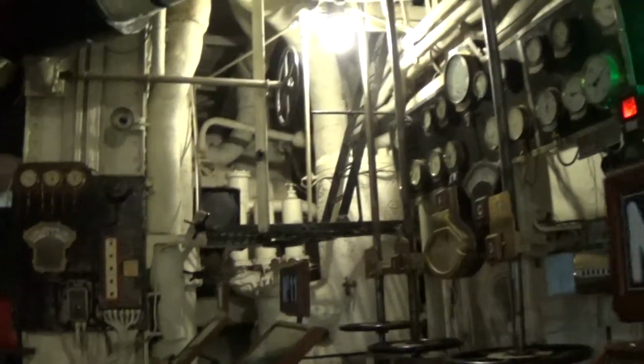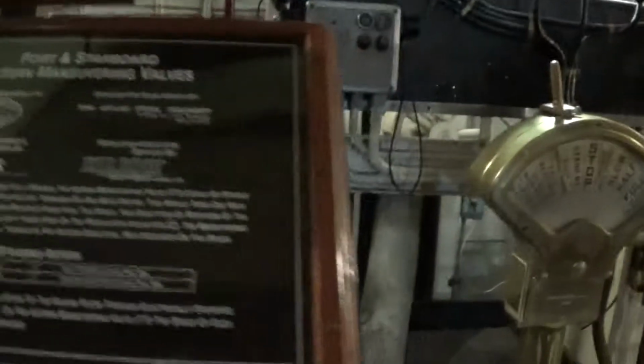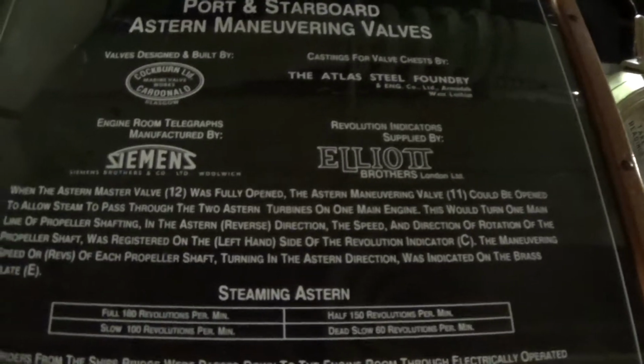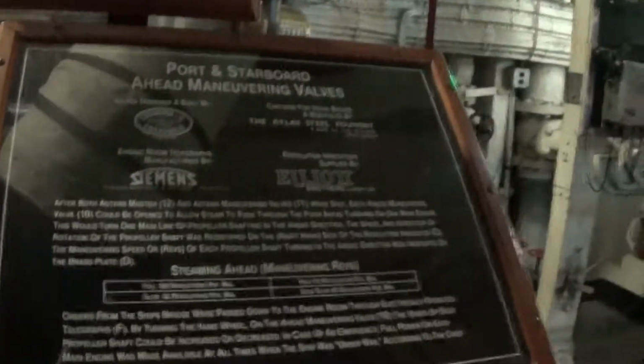In the first stage of steam generation, saturated steam was produced in large vertical tubes and passed to the upper half of the steam water drum. This saturated steam was then passed back into the furnace, where it was superheated in small bore tubes and fed into a superheater header or drum, then passed to the engines at 400 pounds per square inch and 700 degrees Fahrenheit. The hot exhaust gases from the furnace were vented out through stack uptakes or funnels. Numbers 1 and 2 boiler rooms to the forward stack, numbers 3 and 4 boiler rooms to the center stack, and number 5 boiler room to the after stack.